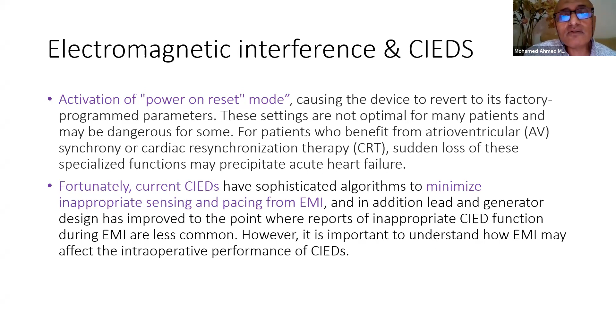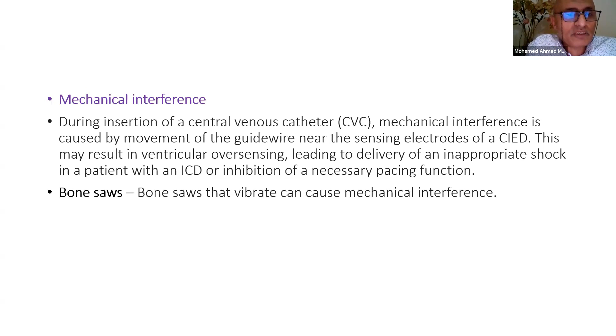Another type of interference is mechanical interference. By mechanical interference, we mean mechanical stimulation or mechanical displacement of the sensing lead of the pacemaker, either during insertion of the CVP catheter, or during the use of a bone saw by the surgeon, or even during shivering in the post-operative period, or during fasciculations due to succinylcholine injection. All these movements can cause mechanical interference with the pacemaker, and it may lead to an inappropriate response from the pacemaker.